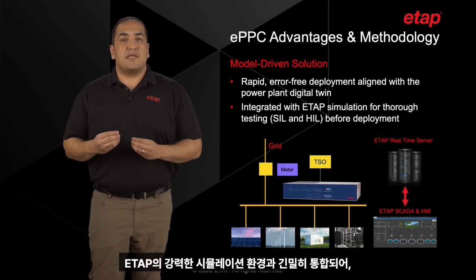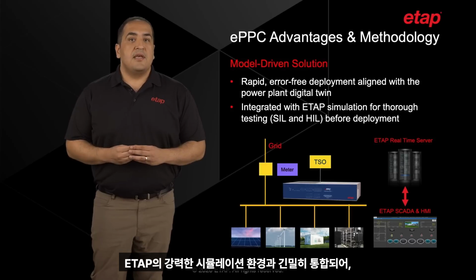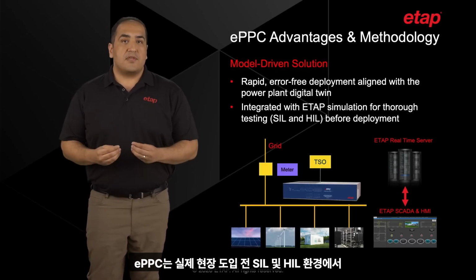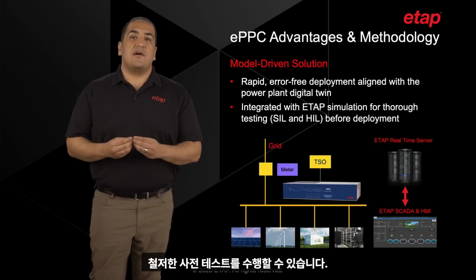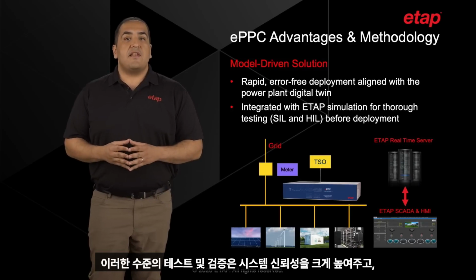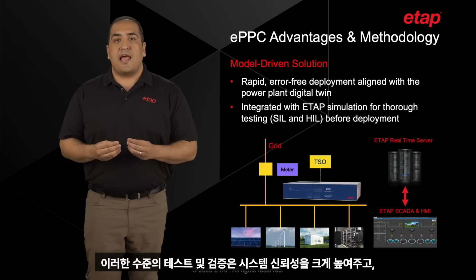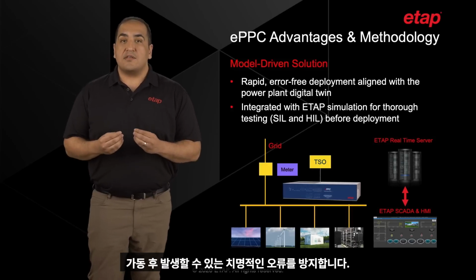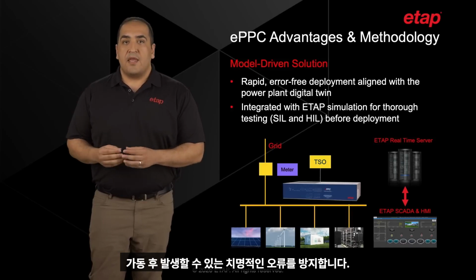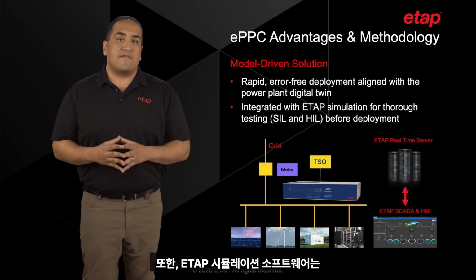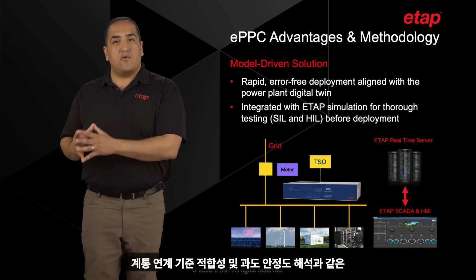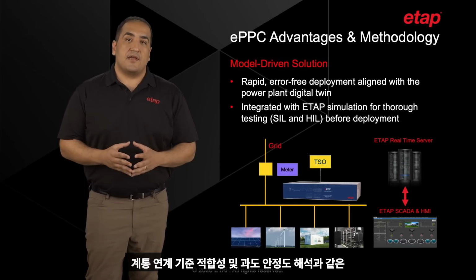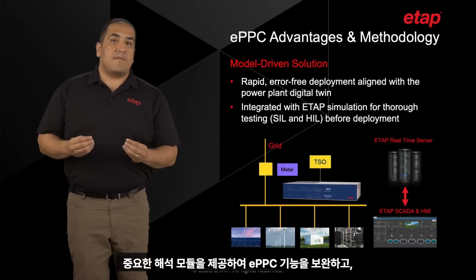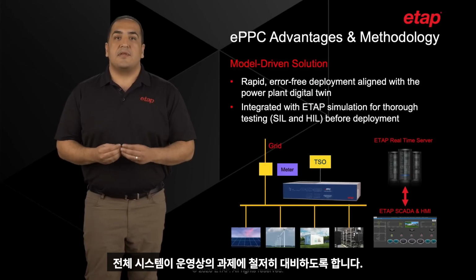By integrating closely with ETAP's robust simulation environment, ePPC allows for thorough testing in both software-in-the-loop and hardware-in-the-loop configurations before any real-world deployment. This level of testing and validation significantly enhances reliability and helps avoid costly errors once the system is live. Additionally, ETAP simulation software offers critical study types like grid code compliance studies and transient stability analysis, which complement ePPC's capability and ensure that the entire system is well prepared for operational challenges.